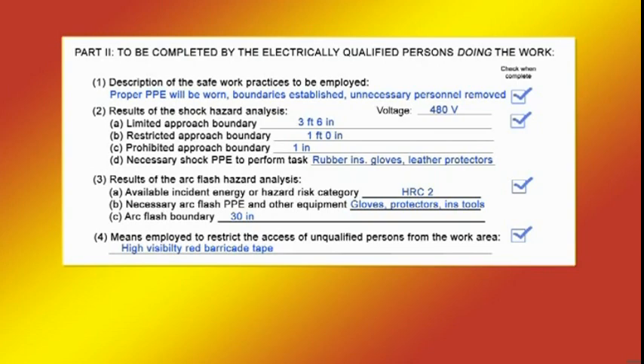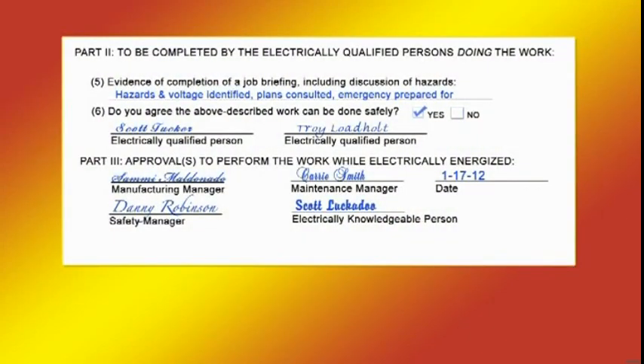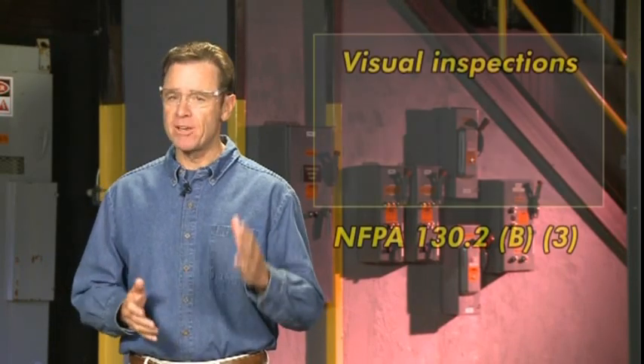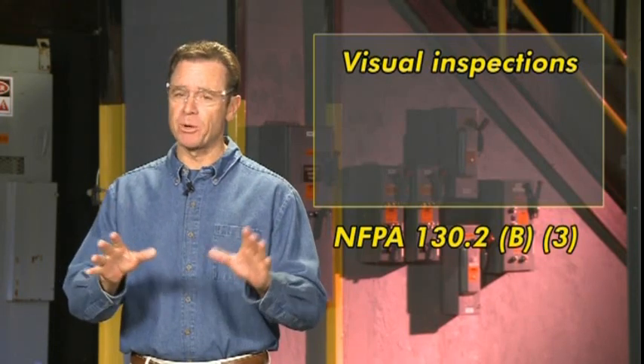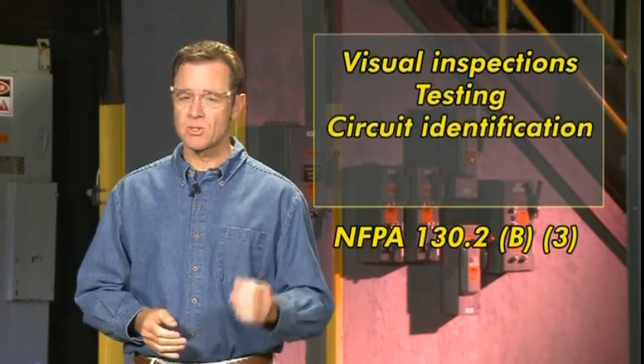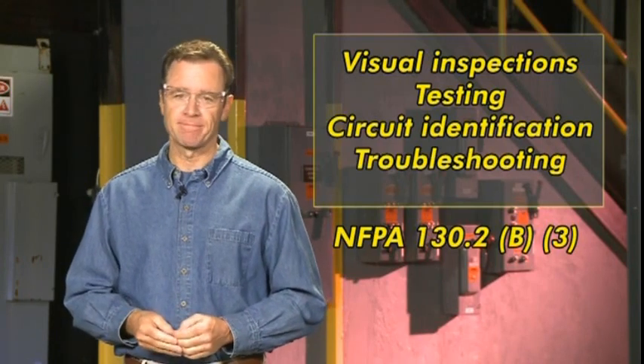The means used to restrict the access of unqualified persons from the work area. Evidence of the completion of a job briefing, which includes any job-specific hazards. And finally, the signature of authorized members of management approving the work to be performed while energized. This approval process must include an electrically knowledgeable person. There are specific exceptions to the requirement for an energized electrical work permit. They are visual inspections if the restricted approach boundary is not crossed, testing, circuit identification, and troubleshooting.